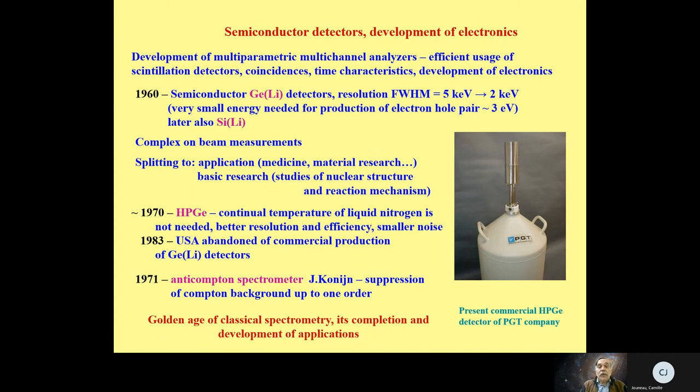That means it is also possible to use it for some factory in which I will use this for some application, and I will make some measurement for 1 week, after that I will end the measurement, and for 2 months it's not necessary for me to have this semiconductor detector working, and I will put away this liquid nitrogen, it is not necessary to have it, and to wait, and after that to start the measurement.